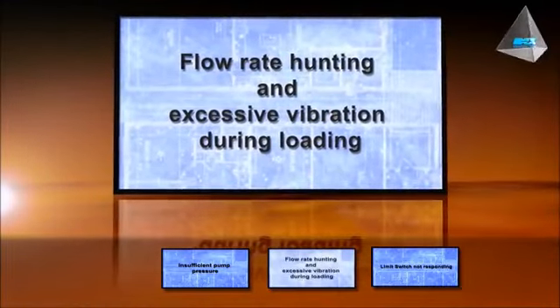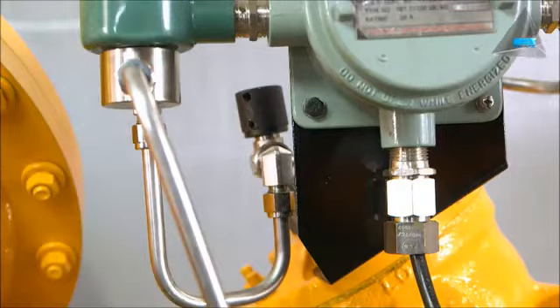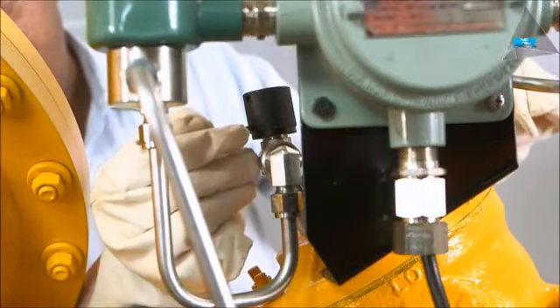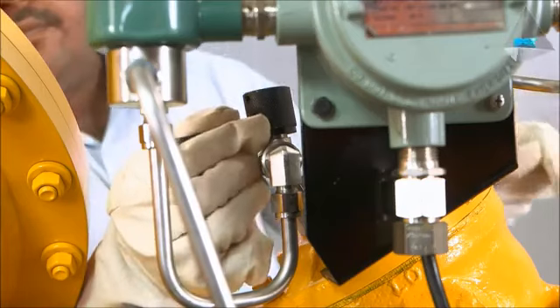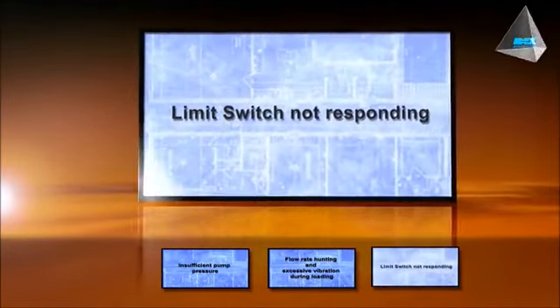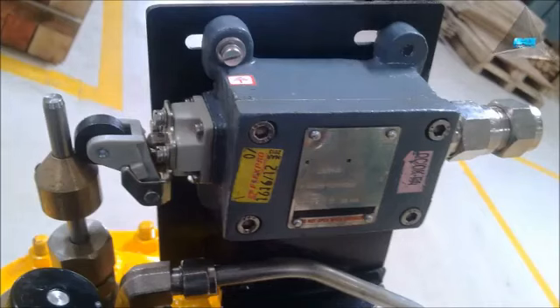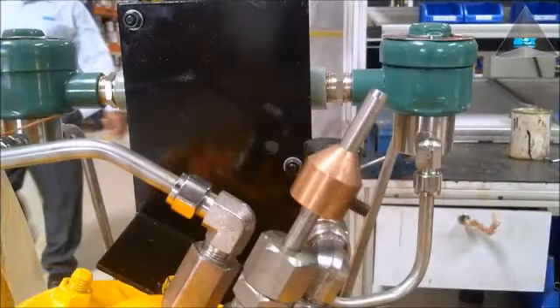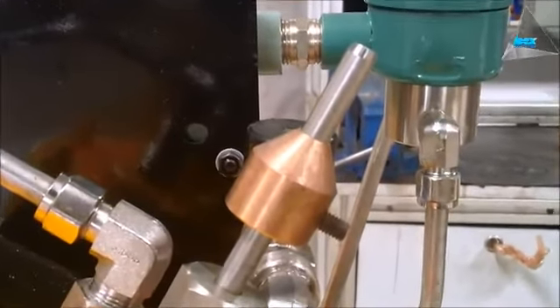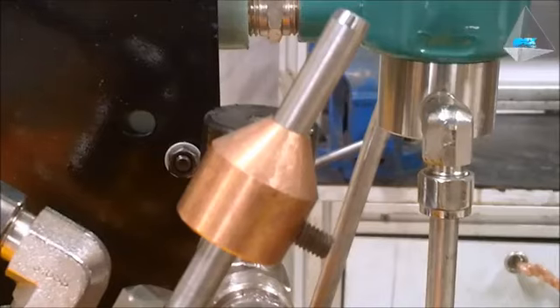Flow rate hunting and excessive vibration during loading. Possible cause: needle valve not properly tuned. Solution: tune the needle valve appropriately. Limit switch not responding. Possible cause: stem assembly jammed. Solution: disassemble and check free movement of the assembly. Replace if required.